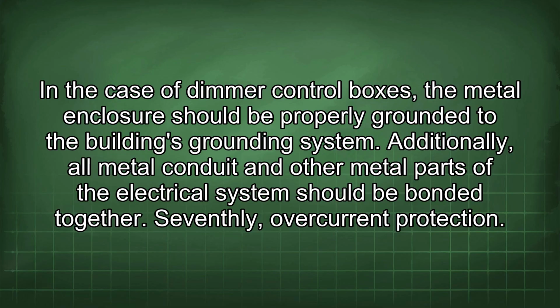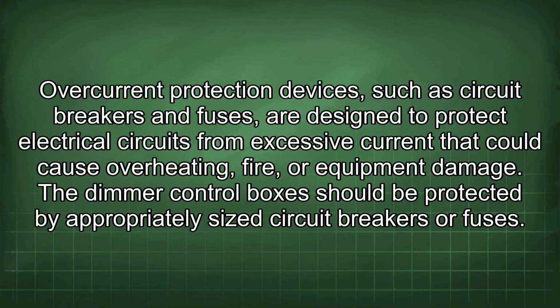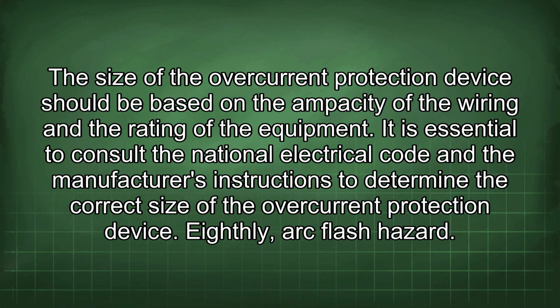Seventhly, overcurrent protection. Overcurrent protection devices, such as circuit breakers and fuses, are designed to protect electrical circuits from excessive current that could cause overheating, fire, or equipment damage. The dimmer control boxes should be protected by appropriately sized circuit breakers or fuses. The size of the overcurrent protection device should be based on the ampacity of the wiring and the rating of the equipment. It is essential to consult the National Electrical Code and the manufacturer's instructions to determine the correct size of the overcurrent protection device.